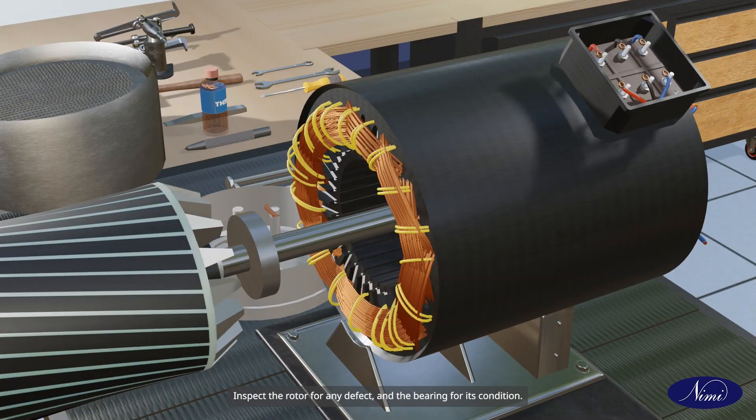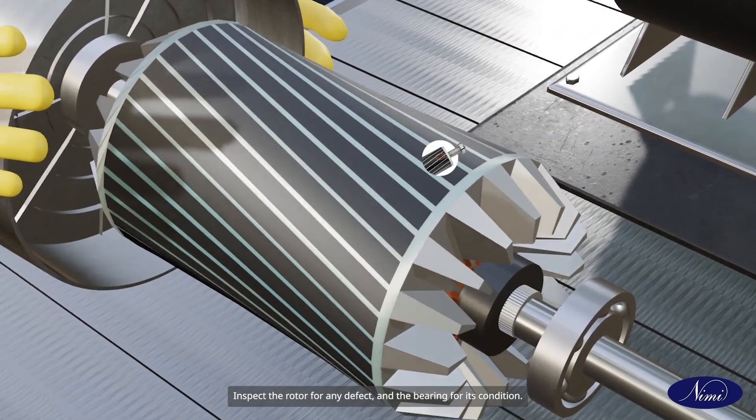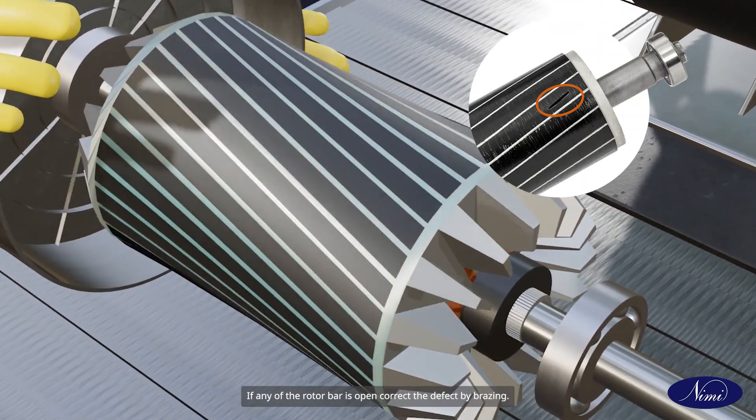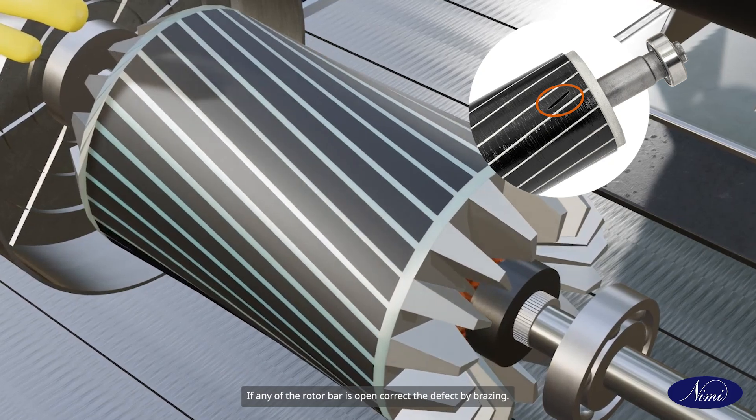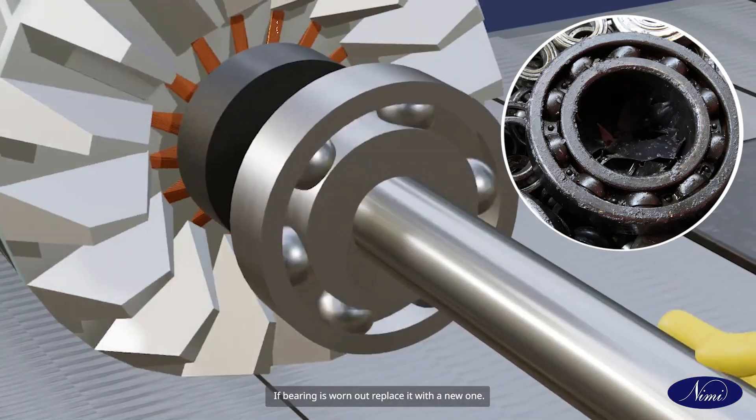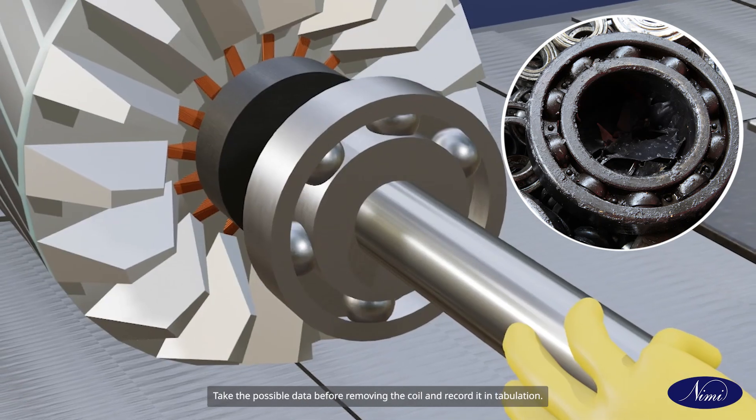Inspect the rotor for any defect and the bearing for its condition. If any of the rotor bar is open, correct the defect by brazing. If bearing is worn out, replace it with a new one.